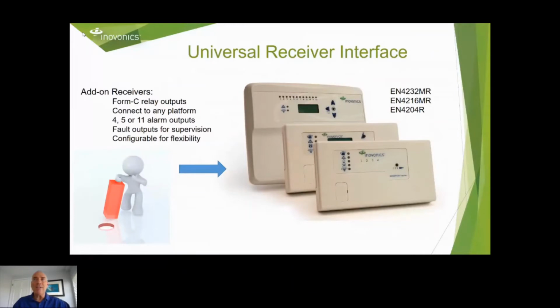For anything else that we don't have a specific interface for, we have these add-on receivers. Many of you are familiar with them. I like to call them small, medium, and large. The EN4204R is a 4-channel. It has a 5th fault relay for your trouble signals. The EN4216MR will handle 16 transmitters. You would zone them out among as many as 5 alarm relay outputs. Then you would have that 6th relay going into a zone on the alarm panel, for example, that you would designate for RF trouble. And if that zone trips, you just go look at the display on the receiver, and that will identify what the fault is.